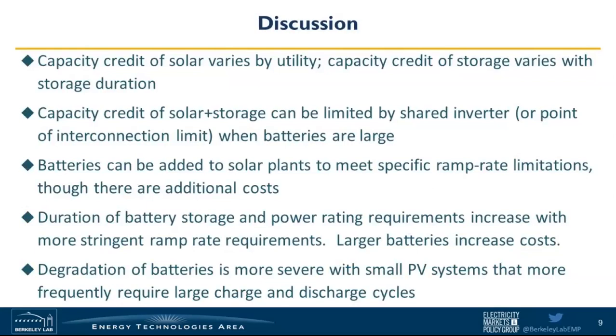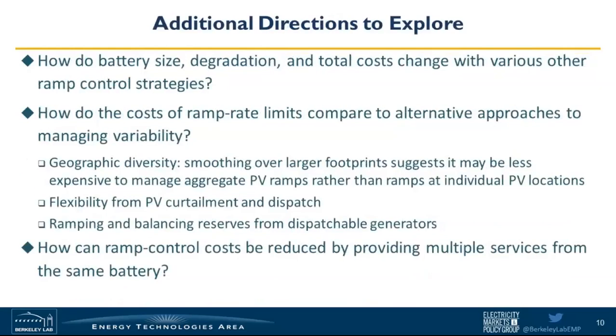Increasing the stringency of that ramp rate limit increases the required battery duration, and therefore also increases the cost of meeting those limits. And finally, we saw that mitigating the ramps for small PV systems has higher costs due to these more frequent large cycles. With this research so far, we've really just scratched the surface of this analysis. And so for refining and expanding the research, we recommend looking at more advanced ramp rate control strategies. We looked at a fairly simple one here.